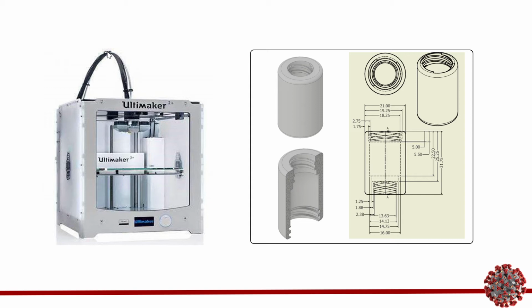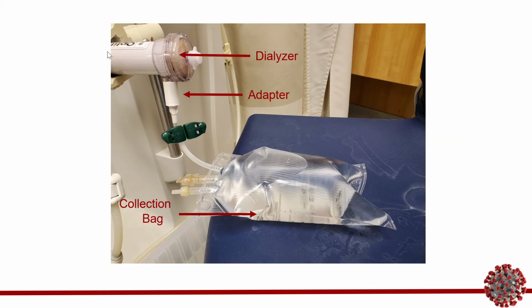We reverse engineered the threads on both the dialyzer and the bag to ensure a tight fit, and adjusted the adapter's length to make sure the fluid did not contact the adapter. Fortunately, we had a 3D printer available for our use, and with just a few printing iterations, we had an operational prototype. Less than 24 hours after being contacted by Dr. Parikh, we traveled to the hospital to test it as part of the completed system. To our delight, everything worked perfectly and the bags filled without leaking any dialysate fluid.